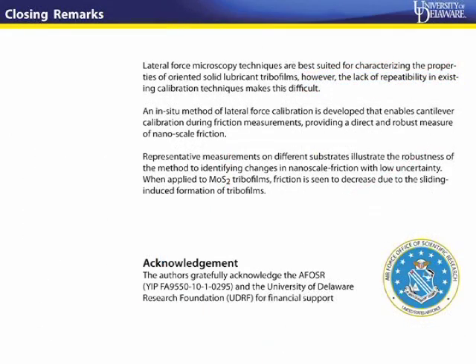So essentially, what we set out to do is present an in situ method of lateral force calibration. Like I mentioned earlier, traditional legacy methods always seek to calibrate the AFM for lateral forces as a separate step from the actual measurement. That in itself provides the opportunity for many uncertainties to show up, just because of the way the instrument is set up, and also because of changes between the calibration step and the measurement step. So we showed that with an in situ method, there is no need for a separate calibration grating.